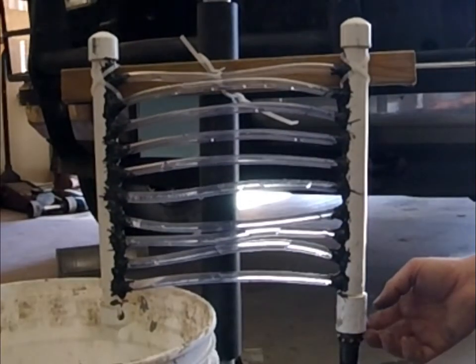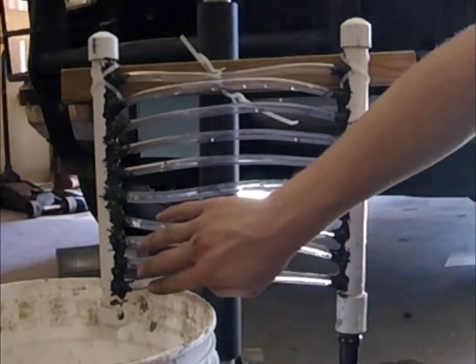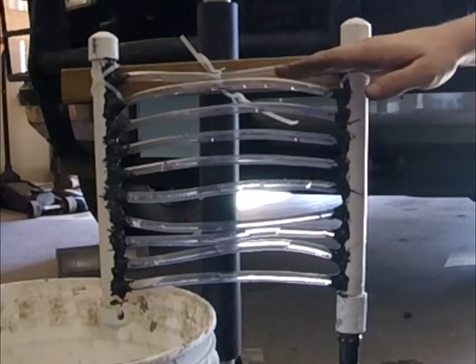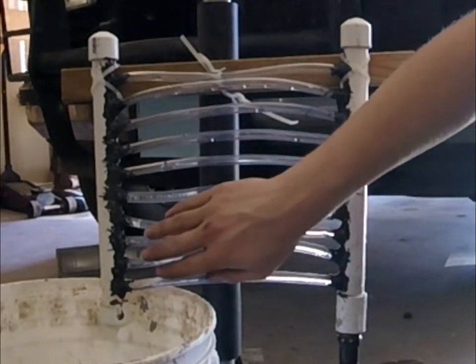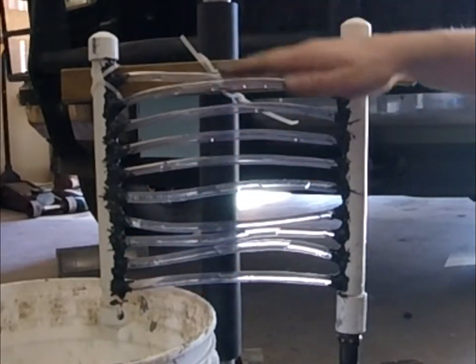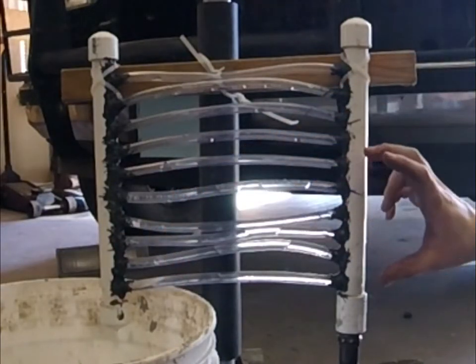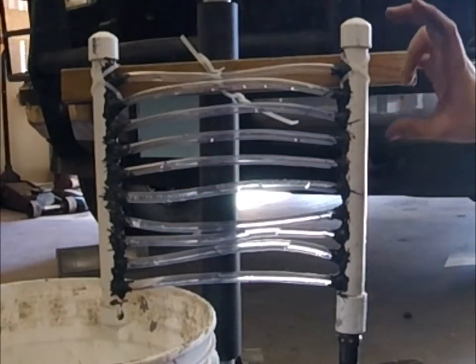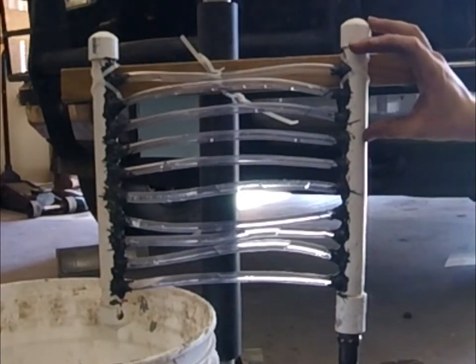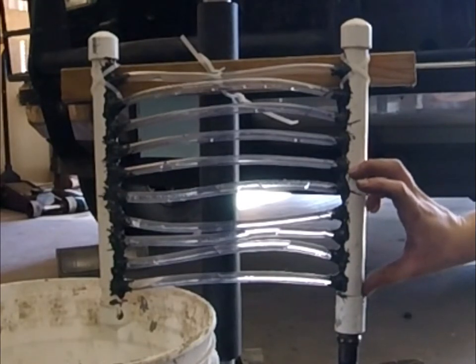Theoretically, at least from what I read online, fluid is going to come up and run across the bottom here. Before the rest of the cooler can fill up, the fluid that runs across the bottom is going to airlock that port. It's going to cover that port up and all the air up here is not going to be able to escape. That's a problem because if you only have half of the cooler full of fluid and the other half airlocked, just full of hot air basically, then you're only using 50% of what the cooler can actually do.